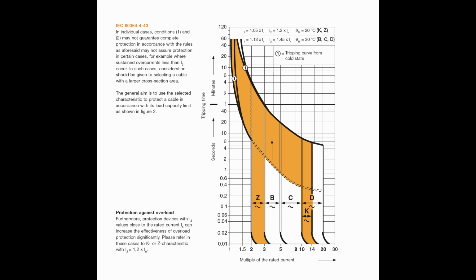And you can see there that if you say applied a current of say 1.5 times, follow the line up there, then it actually basically hits the time at around 20 seconds. Because again, the thermal part is very slow, it takes time to heat up. And of course that's designed for moderate overloads like that. So that does take quite a long time, and again, as we saw before, that is actually the same for all types of circuit breaker. But for the magnetic part, which is essentially the vertical section, it's sort of near instantaneous provided you're within the particular ratings you've got, so say 3 to 5 for the type B and so on.